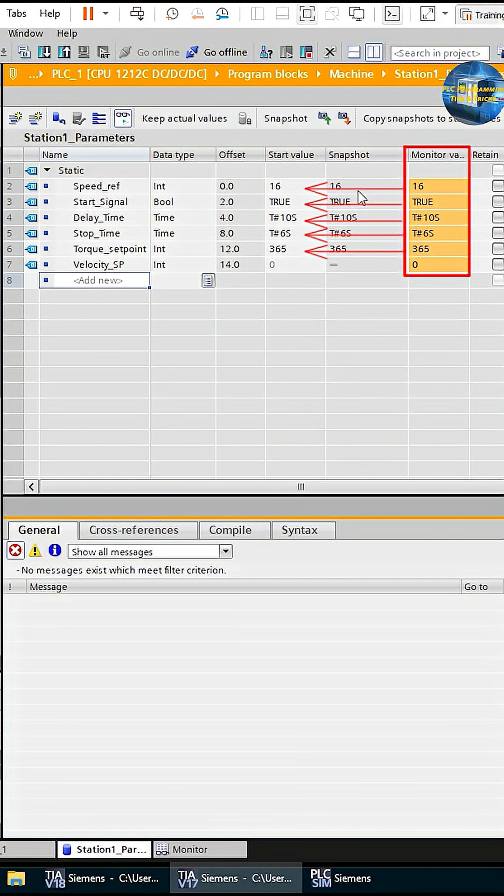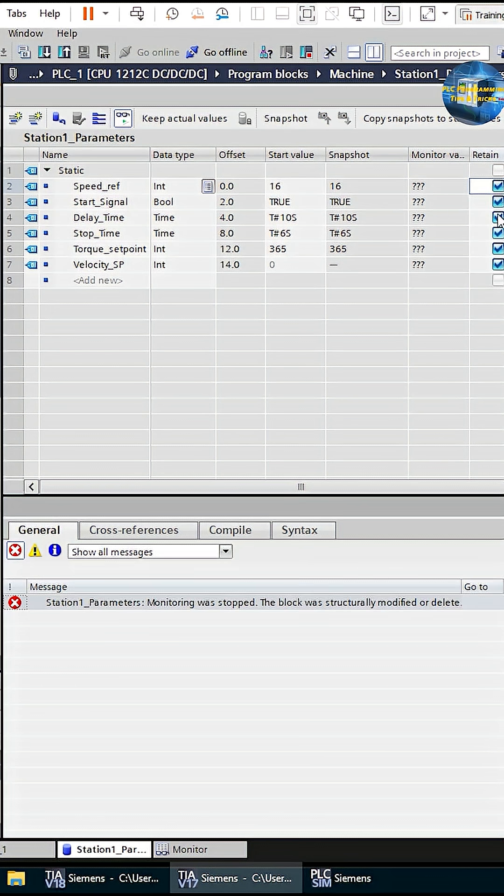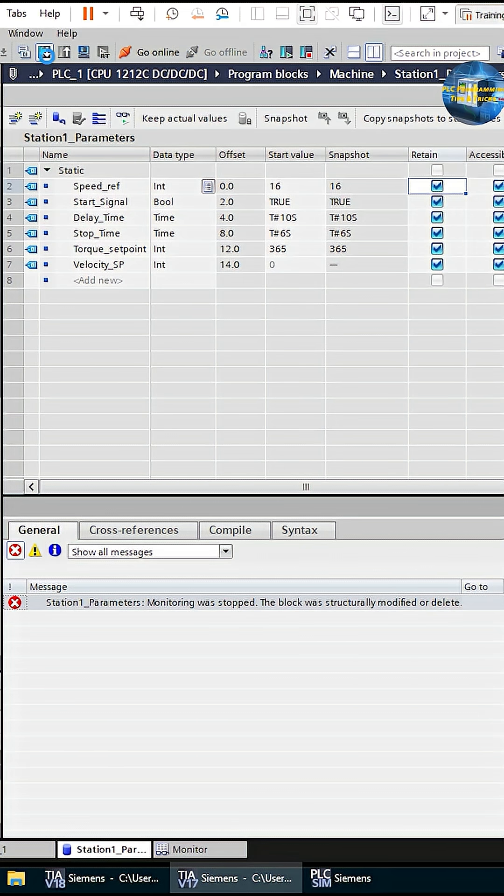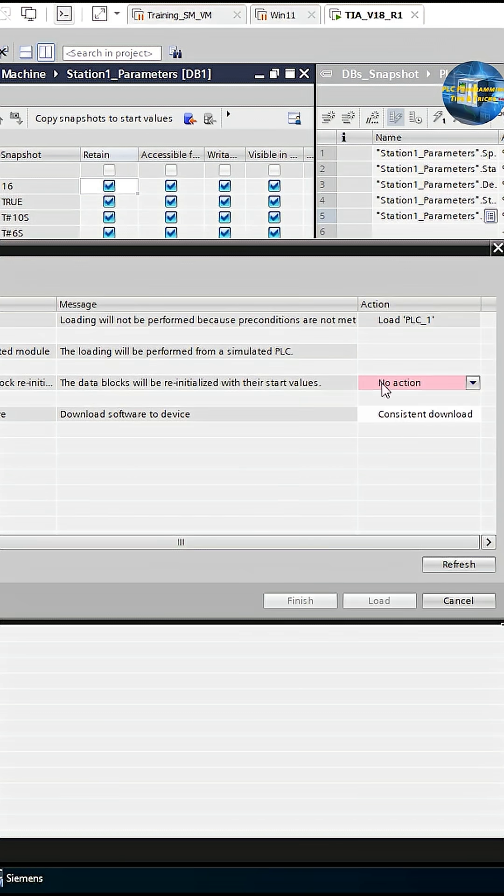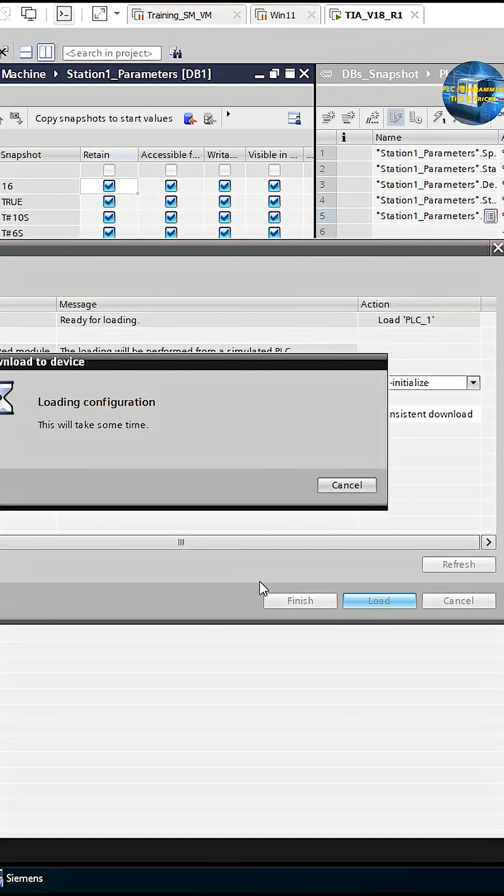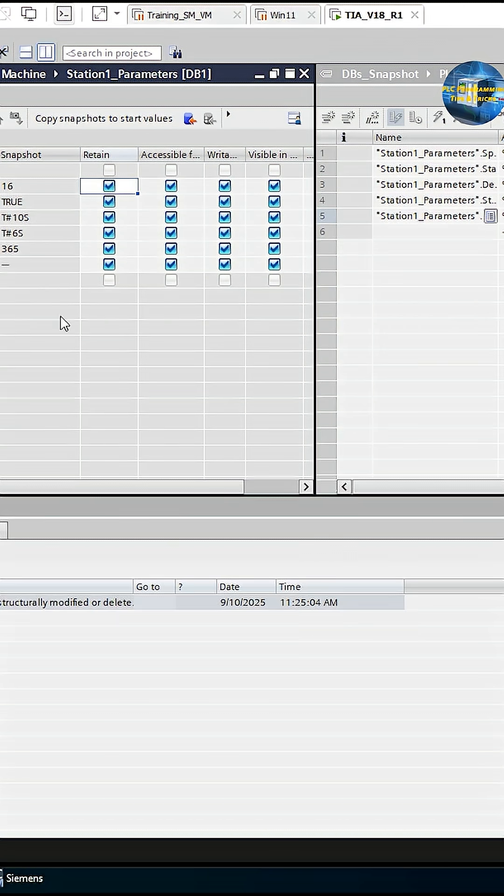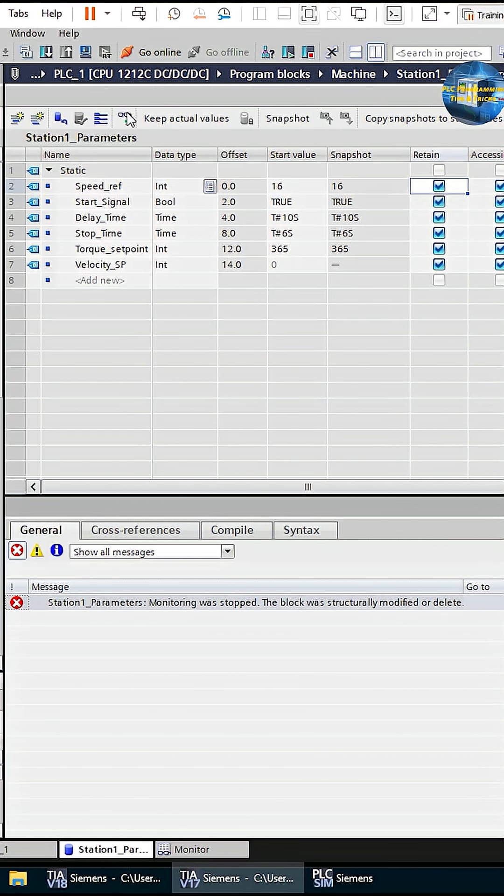The next very important step is enabling the Retain option for these parameters. By enabling Retain, the values in the DB are preserved even after a PLC panel power cycle. And don't forget to download the DBs once more into the PLC after enabling Retain.